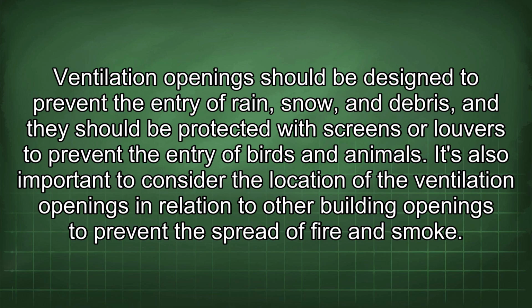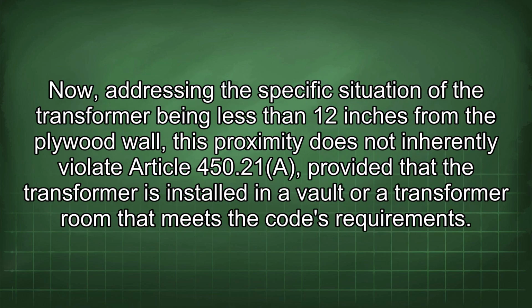It's also important to consider the location of the ventilation openings in relation to other building openings to prevent the spread of fire and smoke. Now, addressing the specific situation of the transformer being less than 12 inches from the plywood wall, this proximity does not inherently violate Article 450.21(A), provided that the transformer is installed in a vault or a transformer room that meets the code requirements.